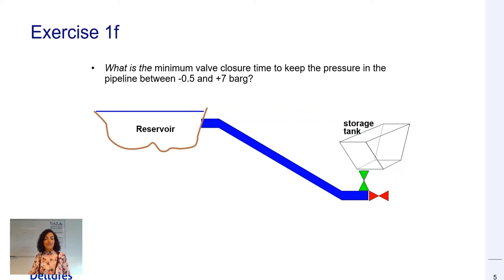Let's assume we have the same gravitational system as before and that we are trying to calculate the minimum valve closure time to keep the pressure in the pipeline between minus 0.5 and 7 bar gauge. Here we are asking ourselves what are the operational conditions at which the pressure wave generated in the system due to a valve closure don't exceed allowable pressure criteria.